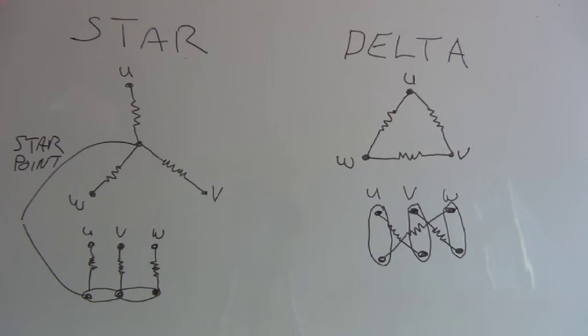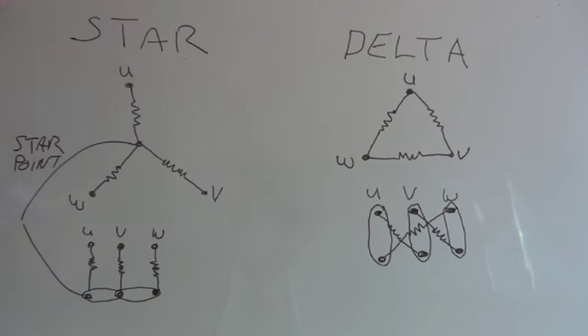When we do the winding balance test, we test if it's the star connection from U to the star point, from V to the star point, and from W to the star point.